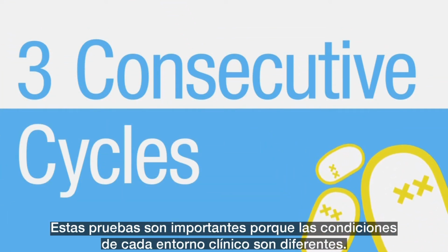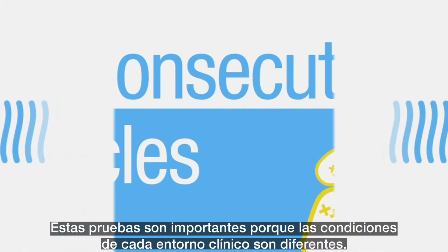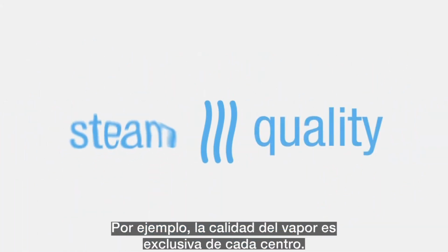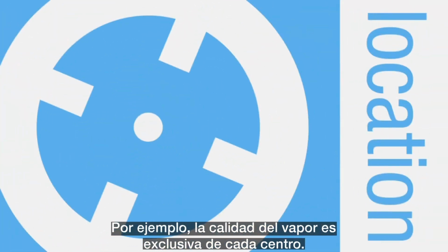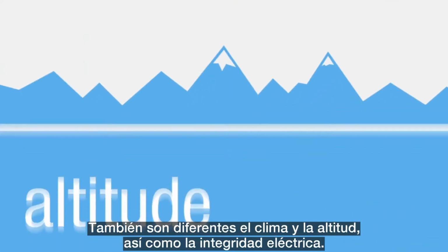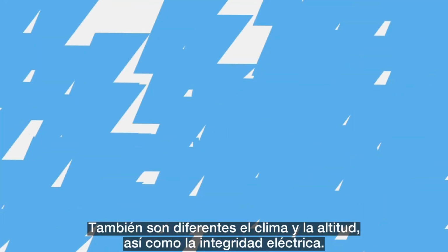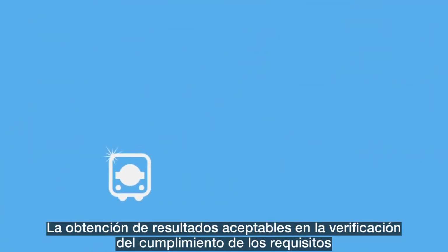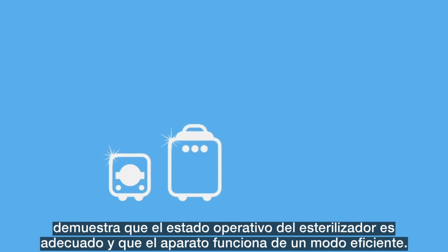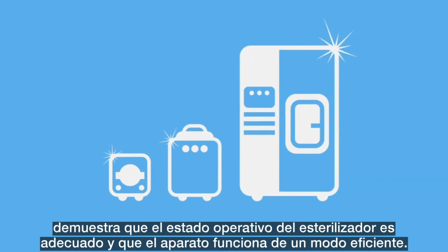These tests are important because the conditions are not the same in every clinical setting. For example, the steam quality is unique to your location, the climate and the altitude are different, and the electrical integrity is not the same everywhere. Acceptable qualification testing results demonstrate that the sterilizer is in good working condition and is functioning effectively.